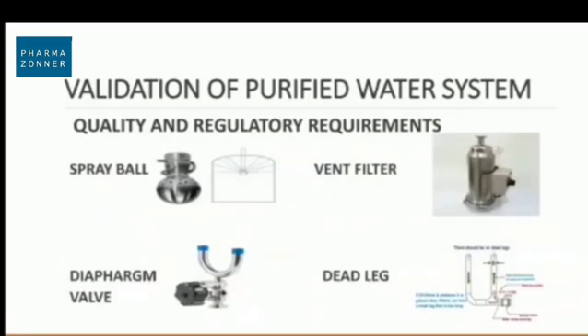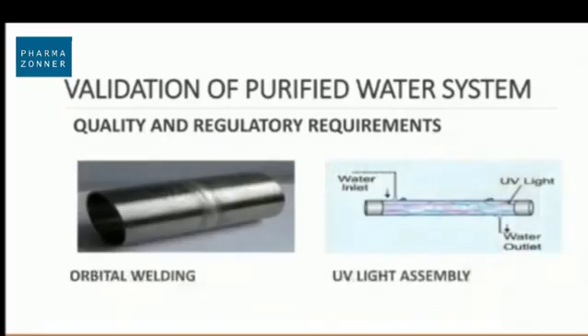Pictures show spray balls, vent filters, and diaphragm valves — diaphragm valves are required as they have zero dead leg. Orbital welding shall be used to connect SS lines; arc welding is not allowed in the water system. UV light assembly is desired after generation of purified water, and most times it is placed in the return loop.